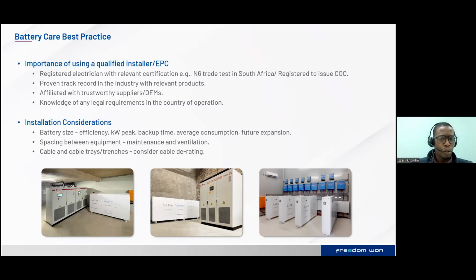Then, looking at the spacing around the equipment that's required, this is quite critical for maintenance purposes and also for ventilation and heat dissipation of the equipment. If you look at the images shown below, the sufficient spacing provided for the equipment allows ease of maintenance and also ventilation. Normally your inverters dissipate a lot of heat. So if your battery is too close to your inverter, you tend to affect the temperature inside the battery. So it's very critical to ensure that your battery and inverter are positioned in such a way that some of the heat is not transferred to the battery.